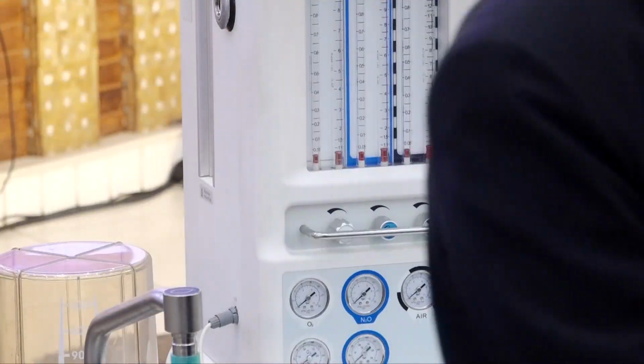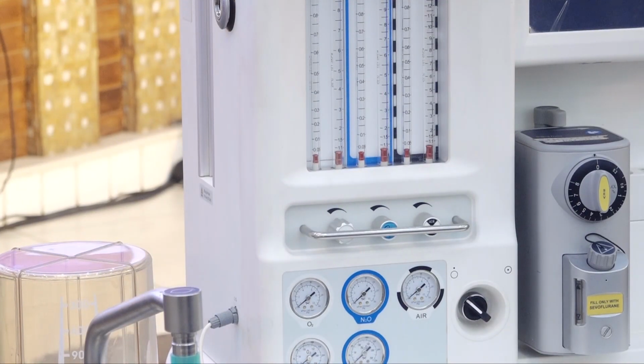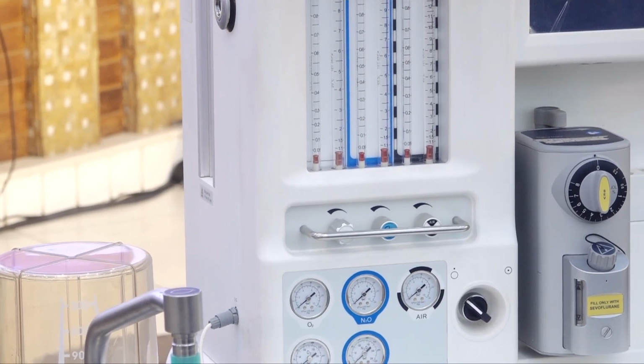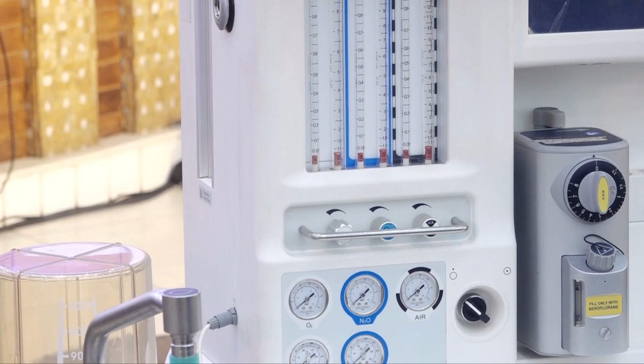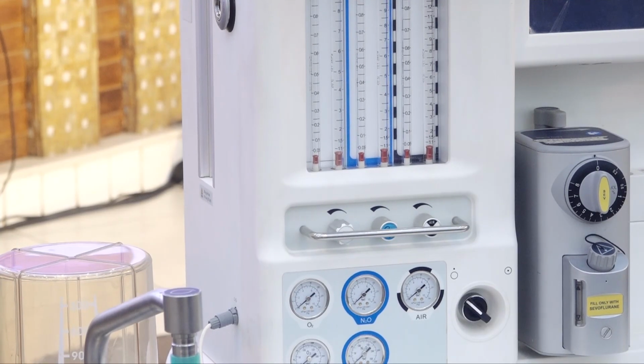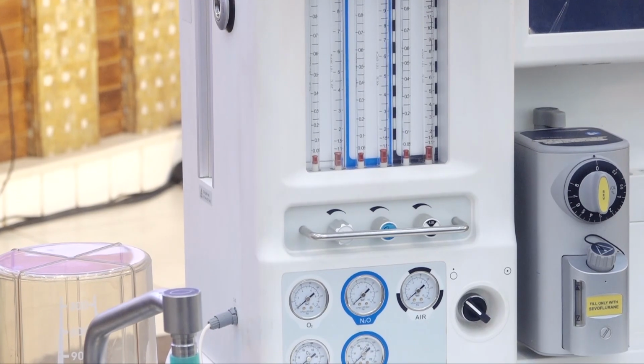And with most modern workstations, you don't have mechanical flow meters. You have electronic flow control. And there are a lot of advantages with electronic flow control. One advantage is you cannot give a hypoxic mixture. So the minimum FiO2 you can go for is 25%. You cannot go less than 25%. So that is one advantage. Second advantage, you don't go for so many liters of flows. You just set the FiO2 to this much and the total flows.